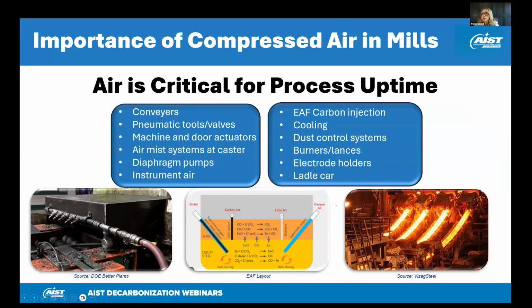We're going to look at the importance of compressed air in steel mills. We mentioned that compressed air is critical for the applications of steelmaking and process uptime. The goal today is to give you the knowledge of where to find the opportunities to improve the system efficiency and where those opportunities are in the mill. So you can find them where compressed air is being used, and that's for conveying applications, pneumatic tools and valves, machines and door actuators, also the furnace door actuation, air mist systems, instrument air, carbon and lime injection for the electric arc furnace, cooling, bag houses, burners, lances, ladle cars, etc. So there's many applications, and we'll go through applications for both integrated mills and electric arc furnaces in this presentation.